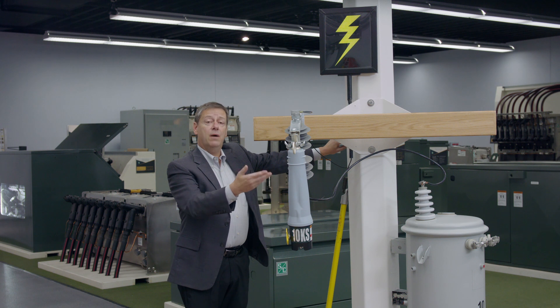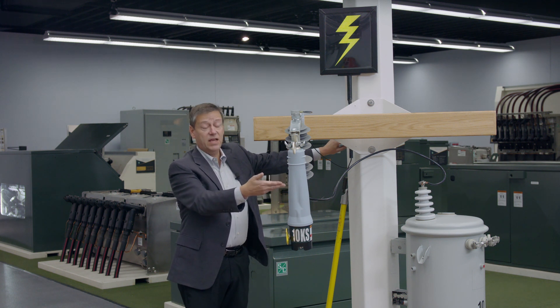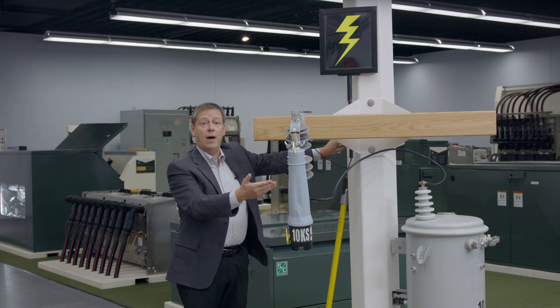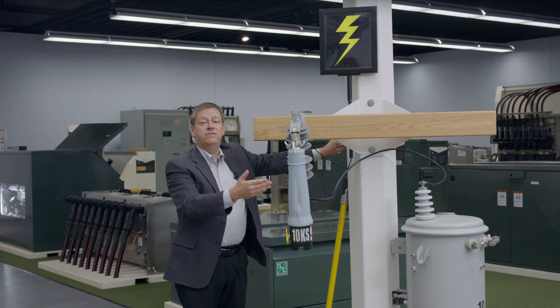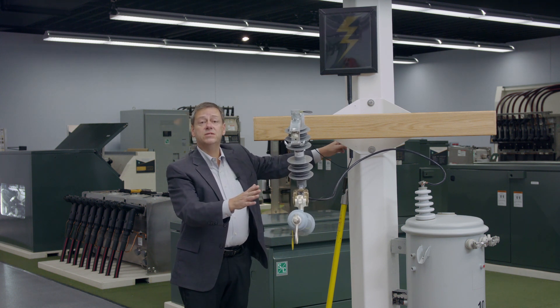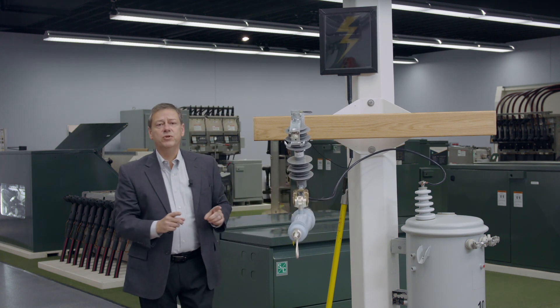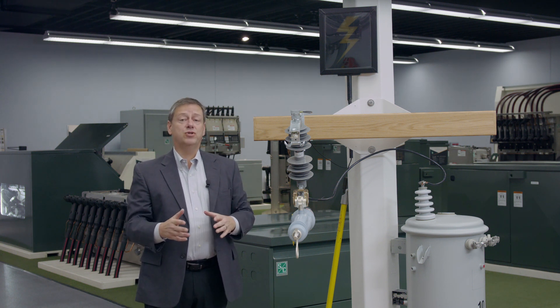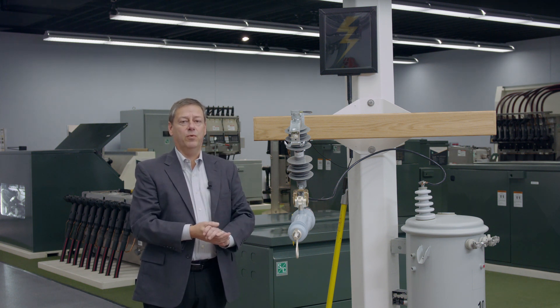It's going to come back in about 20 seconds and close back in. It sees that the fault is still there, so now it's locked out and in a few seconds it will drop open. This will leave the line crews with a visible marker to make it very easy to detect and find where the problem is and repair it. This can be particularly helpful when transformers are hidden behind trees, buildings, or other common obstructions and can't immediately be seen from the road.